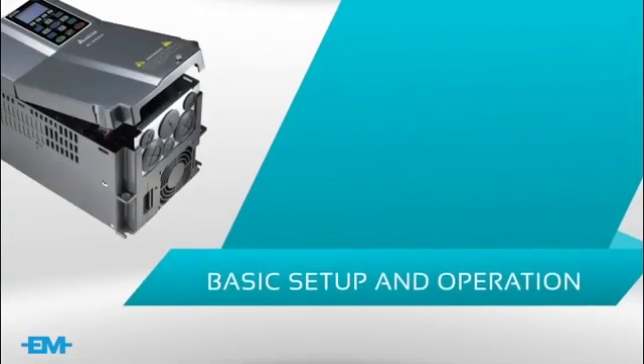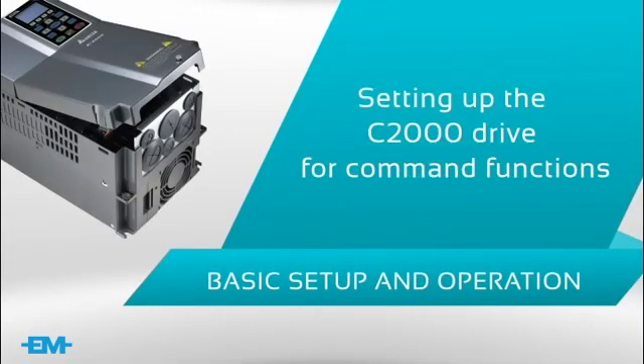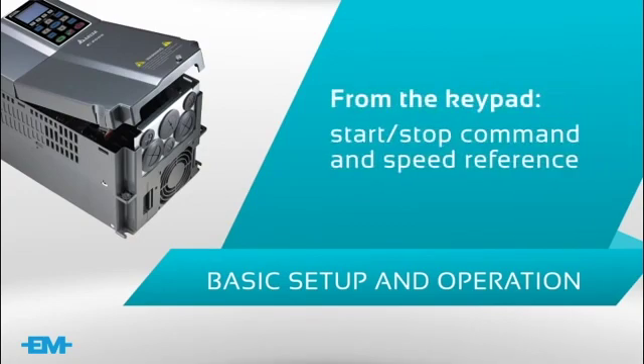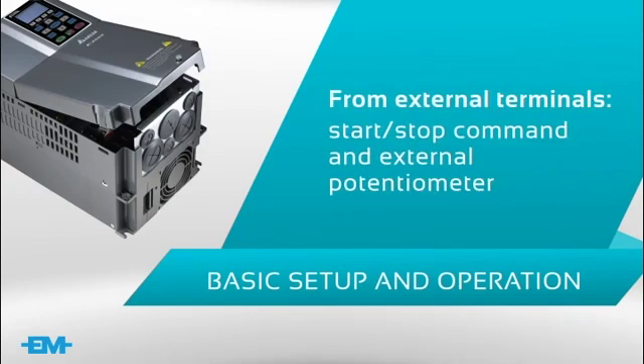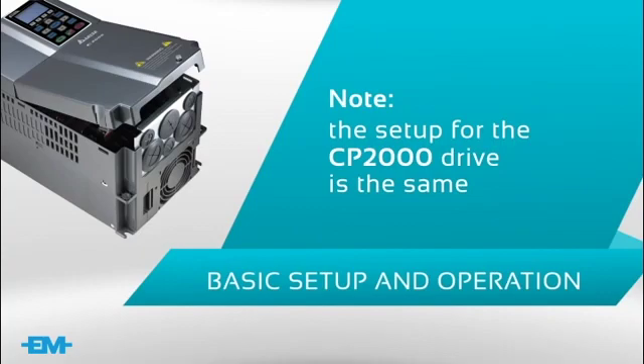We are going to demonstrate how you would set up the C2000 drive for the following command functions: from the keypad, start-stop command and speed reference; and from external terminals, start-stop command and external potentiometer. Note, the setup for the CP2000 drive is the same.